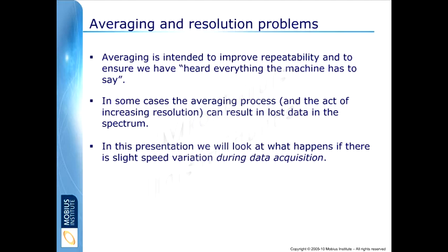As the shaft turns and the balls roll around, there's going to be times when as those balls are perhaps spinning in the bearing, they'll impact sometimes, they won't other times on both races. If you've got a gearbox there can be teeth that come into mesh just so often, so you don't want to have a measurement that's too quick. So averaging does a number of things for us. Improves our repeatability, reduces the impact of noise, and makes sure that we've heard the machine through all its variation and heard its whole story.